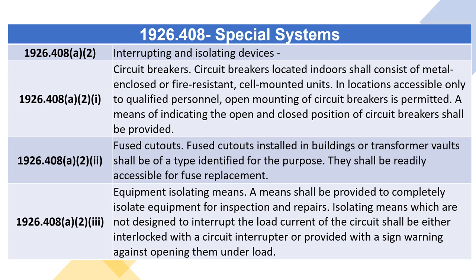1926.408(A)(2)(ii) — Fused Cutouts. Fused cutouts installed in buildings or transformer vaults shall be of a type identified for the purpose. They shall be readily accessible for fuse replacement. 1926.408(A)(2)(iii) — Equipment Isolating Means. A means shall be provided to completely isolate equipment for inspection and repairs. Isolating means which are not designed to interrupt the load current of the circuit shall be either interlocked with a circuit interrupter or provided with a sign warning against opening them under load.